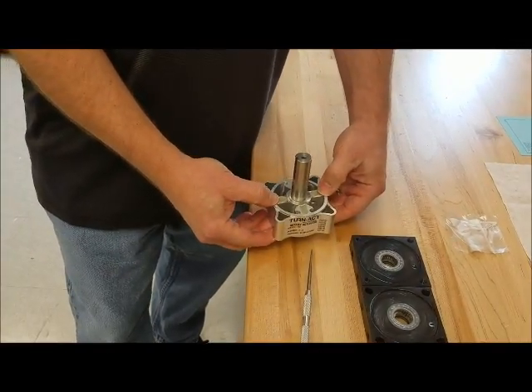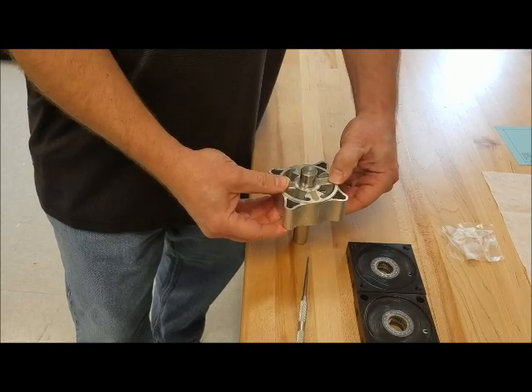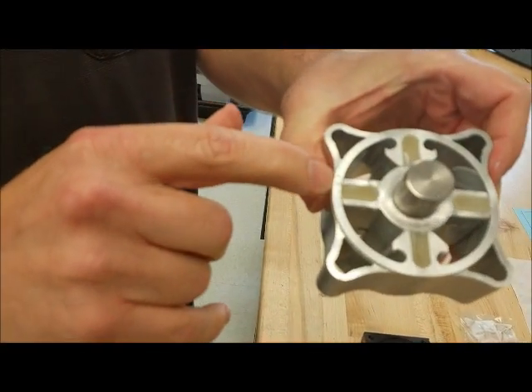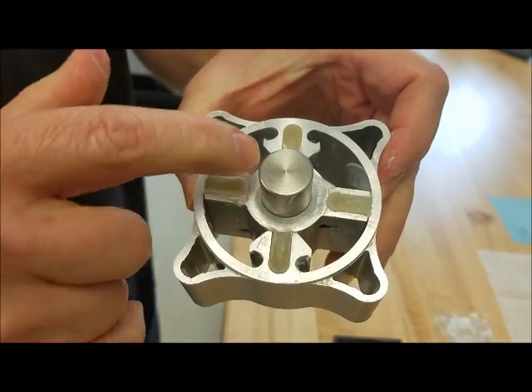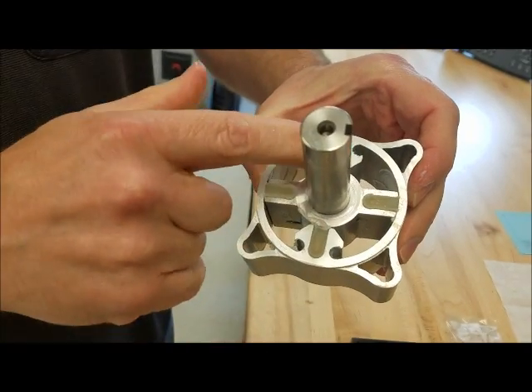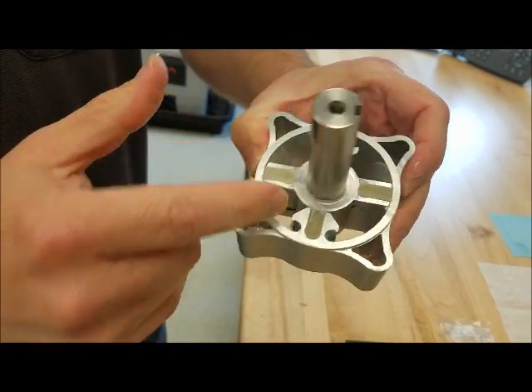Your rotor seals need to stick over the side of the tube and your stator seals in the tube need to stick over the ends of the rotor. So if you'll see here and here and here and here, they are all showing over the ends of the rotor and the tube. You want to make sure that is done.